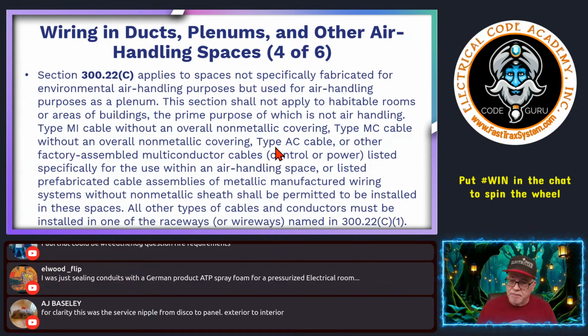Okay. Type AC cable is fine up there as well, or other factory assembled multi-conductor cables, power or control, listed specifically for use within an air handling space, listed prefabricated cable assemblies of metallic manufactured wiring. Maybe there's lighting systems that come with their own metal system that interlocks and connects. That's perfectly fine as long as it doesn't have any non-metallic sheathing on it. Okay.